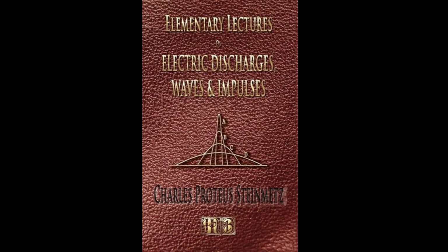As seen, in the ironclad transient the current curve is very much steeper in the range of high currents, where magnetic saturation is reached, but the current is slower in the range of medium magnetic densities. Thus, in ironclad transients very high current values of short duration may occur, and such transients, as those of the starting current of alternating current transformers, may therefore be of serious importance by their excessive current values.